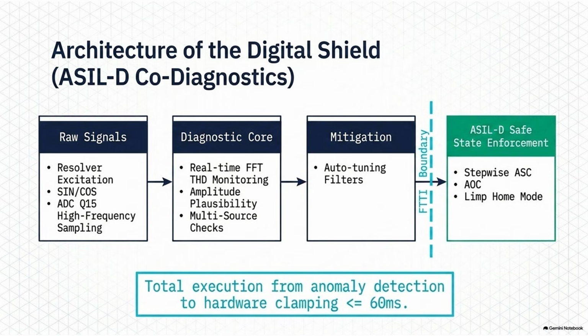The resolver signal just vanishes into the static for a millionth of a second here, a millionth of a second there. But to a motor spinning at 12,000 RPM, a microsecond blind spot is an eternity, isn't it? It's massive. The system completely loses track of the rotor. The maestro just drops the baton. And there it is. That is the full anatomy of the failure, from start to finish. Let me just recap this because it's wild.